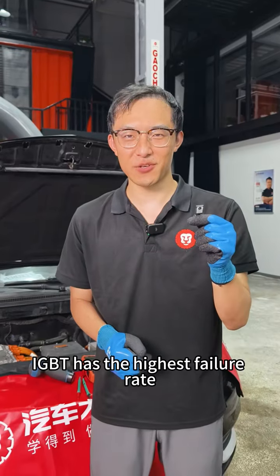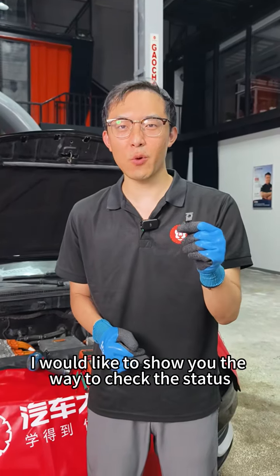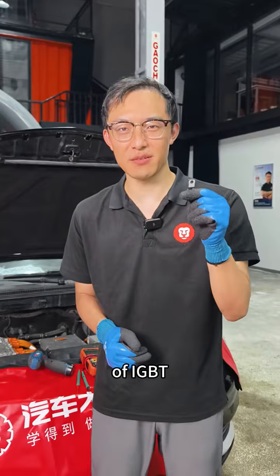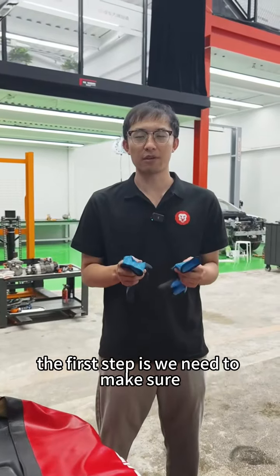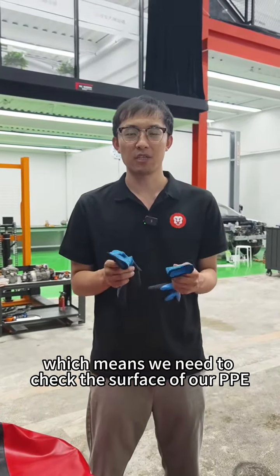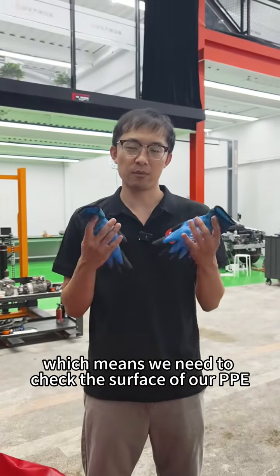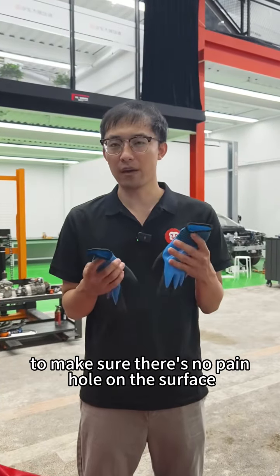IGBT has the highest failure rate. Today, I would like to show you the way to check the status of IGBT. The first step is we need to make sure ourself is well protected, which means we need to check the surface of our PPE to make sure there's no pinhole on the surface.